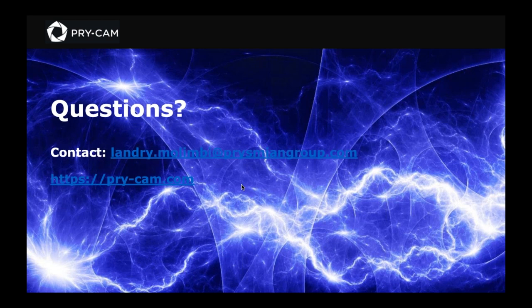As I said at some point in the presentation, the objective was not to dig too deep into the sensing technologies. However, when it comes to DAS, we have tested it for underground cable and submarine cable applications up to 70 kilometers, and we believe that within 70 kilometers we can accurately detect faults and prevent third-party intrusion.